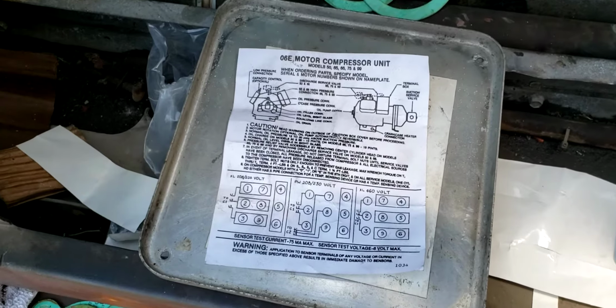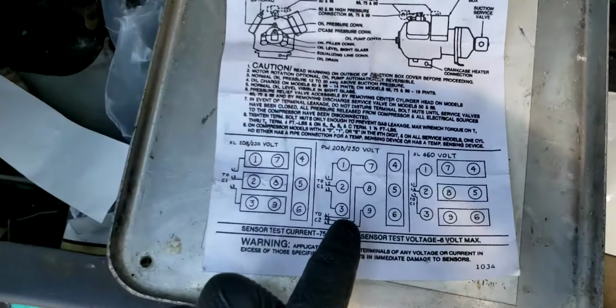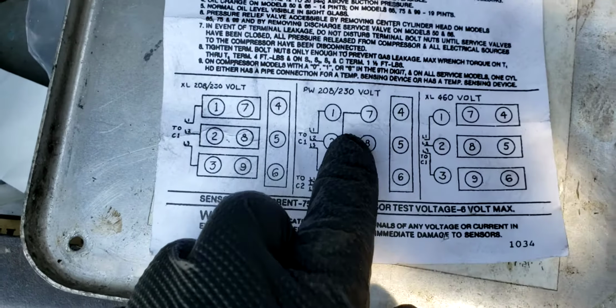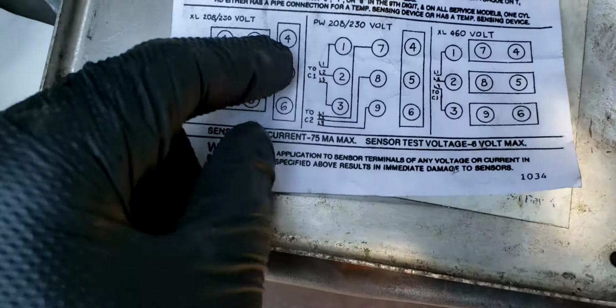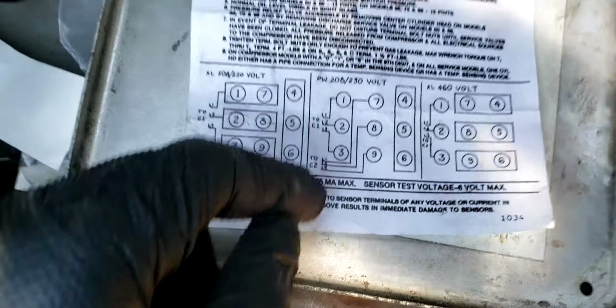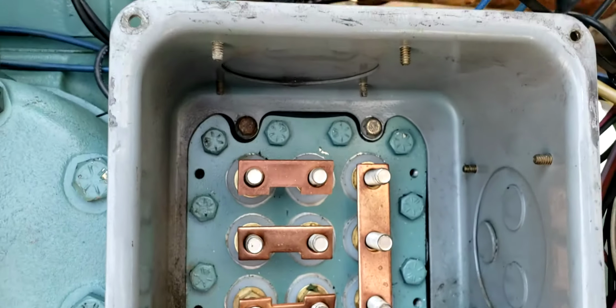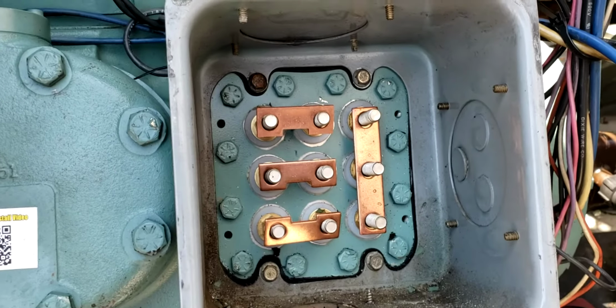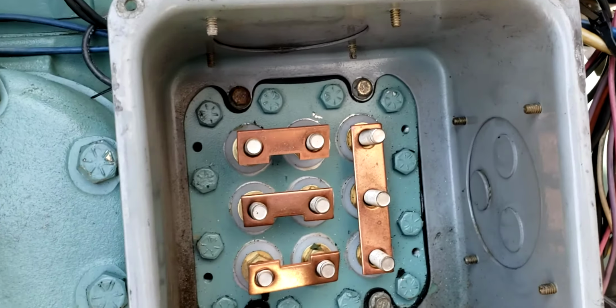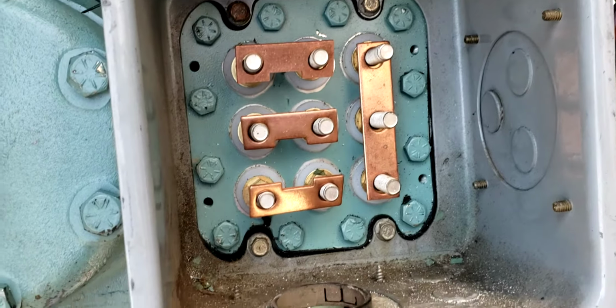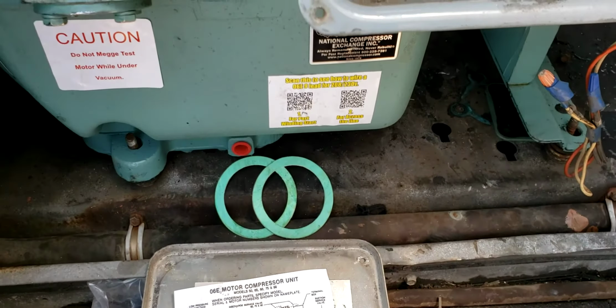You've got to be careful with that. When you're doing the part winding option, you have to make sure your phases are in sync for both contactor 1 and contactor 2. Now, you might ask, what's the whole point of part winding if we have contactor 1 and contactor 2?